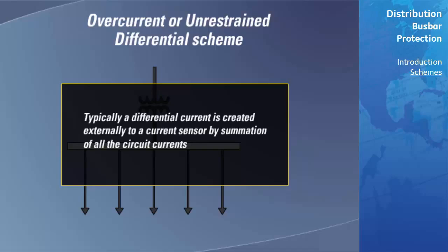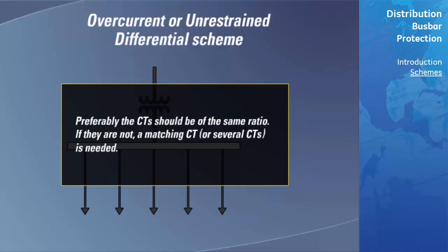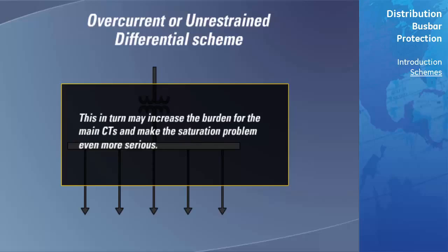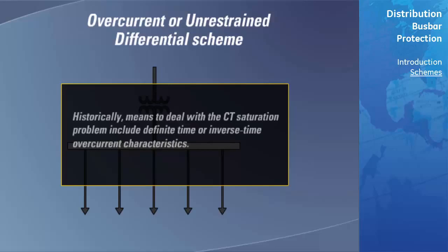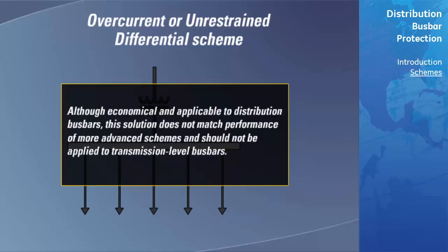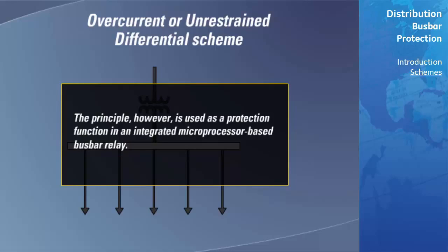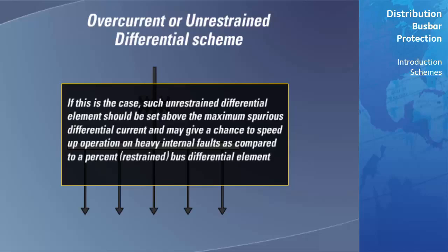Typically, a differential current is created externally to a current sensor by summation of all the circuit currents. Preferably, the CTs should be of the same ratio. If they are not, a matching CT or several CTs is needed, which may increase the burden for the main CTs and make the saturation problem even more serious. Historically, means to deal with the CT saturation problem include definite time or inverse time overcurrent characteristics. Although economical and applicable to distribution bus bars, this solution does not match the performance of more advanced schemes and should not be applied to transmission-level bus bars. The principle, however, is used as a protection function in an integrated microprocessor-based bus bar relay. In such cases, unrestrained differential elements should be set above the maximum spurious differential current and may speed up operation on heavy internal faults compared to a percent or restrained bus differential element.